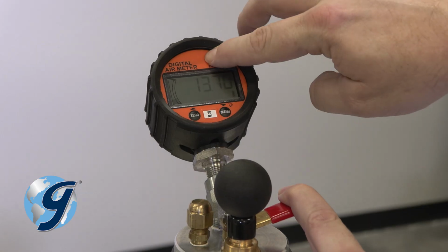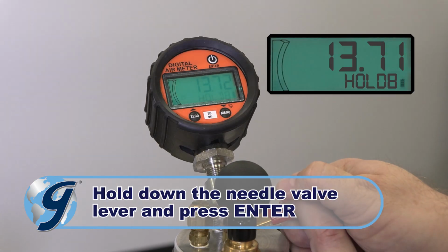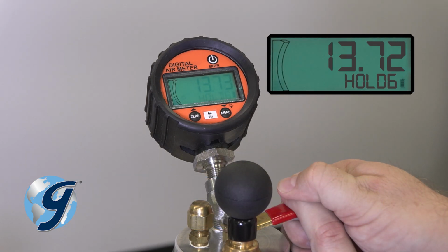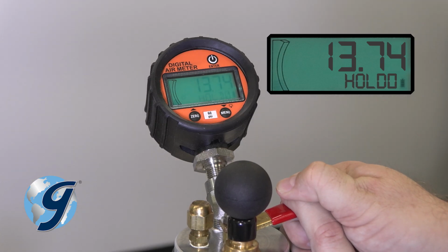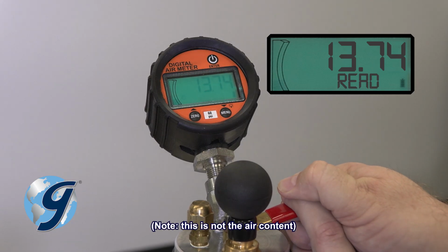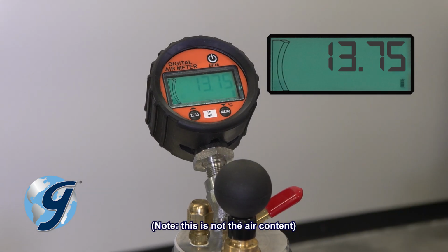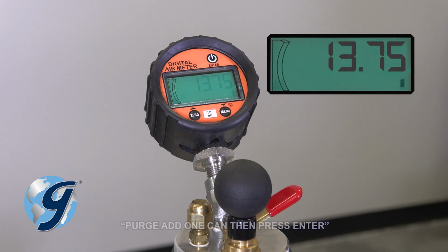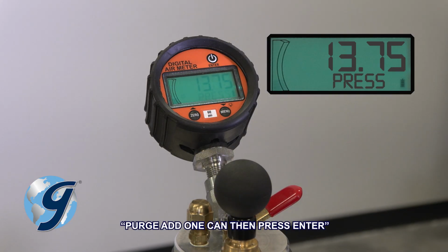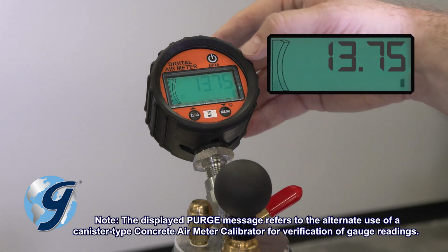Now, when prompted by the gauge, hold down the needle valve lever and press Enter. The gauge will perform a 10-second countdown, then will indicate when to release the lever. The pressure will be shown on the gauge. The gauge will have a purge displayed. This prompt should be ignored by pressing Enter to bypass this message.